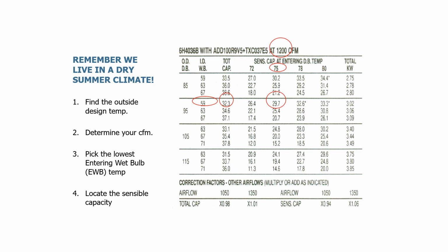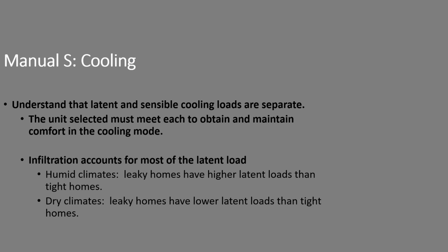And then locate the sensible capacity. Here we have the total capacity, and again, that's the sensible plus the latent. And here, our 3-ton machine is giving us 30K with the sensible capacity, which is really good. Please notice if we pick 67, the sensible capacity drops all the way down to 20, but the total capacity goes up to 37. I really urge you when sizing your air conditioners in the Northwest to pick the lowest indoor wet bulb you can. That's the best indication of the sensible capacity, that ability to lower the dry bulb temperature in the house.